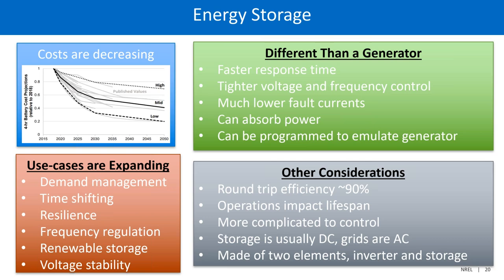0.9 megawatt hours out of it. Operations can have a large impact on lifespan. The more you cycle it, and the higher you charge and discharge it, the shorter amount of time it's going to last. If you charge it to 100% and discharge it to 0%, and you do that 10 times a day, the battery's probably not going to last more than a couple of years. Whereas if you're going between, say, 40 and 60%, and only doing that once a day, it could last 30 years. So operation makes a big impact.